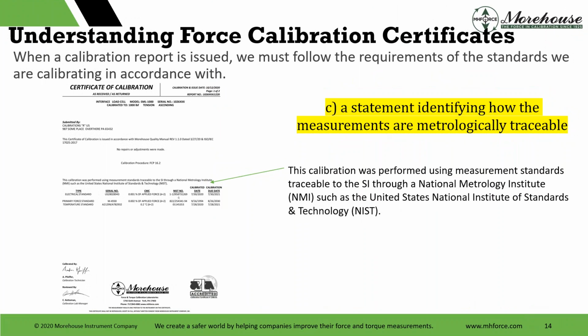A statement identifying how. So remember we talked about traceable to NIST and how that's not good. It's essential to have a chain of traceability in which uncertainty is propagated correctly. That's the uncertainty propagation paper. However, traceability is not to NIST. No. When calibrating load cells, many laboratories fail to get the metrology aspects correct and improperly state NIST traceable master standards, or traceability to NIST, NIST traceable. Anything, any combination of it. At Morehouse, we have seen all sorts of incorrect uses of NIST traceability. So the next time you see a NIST traceable statement, question it, as that statement is not correct.